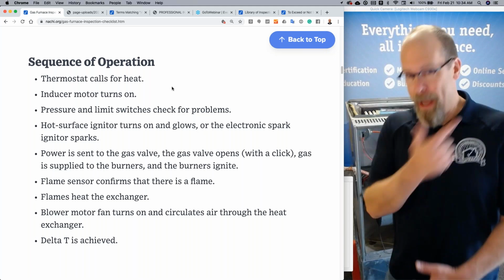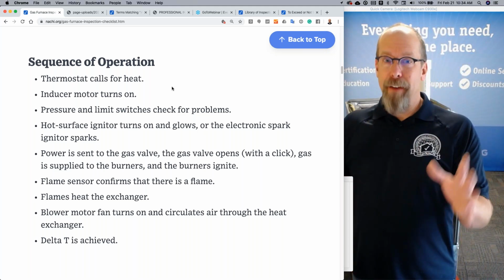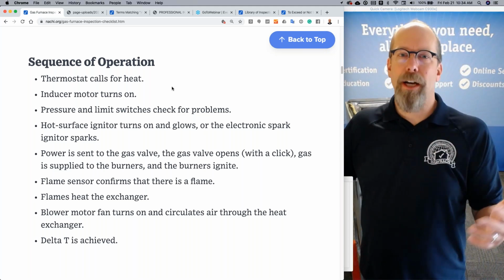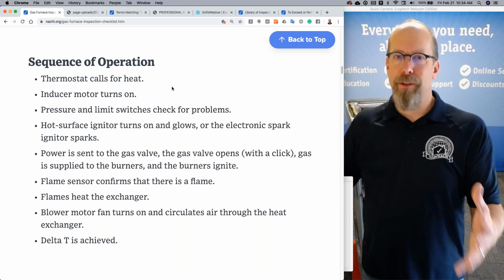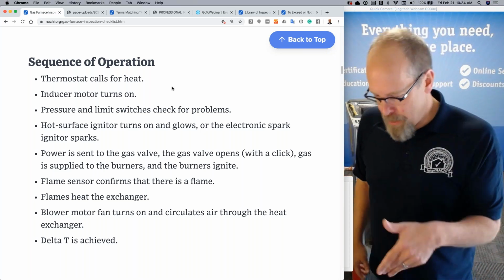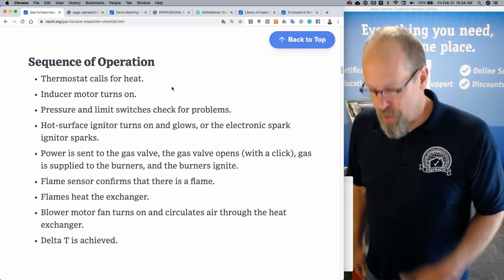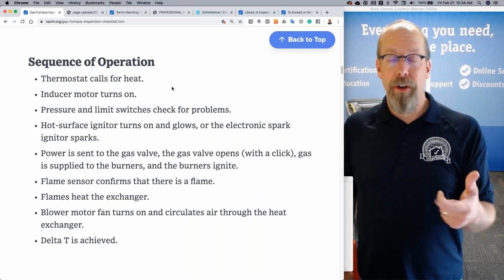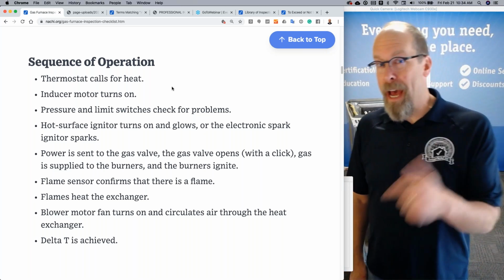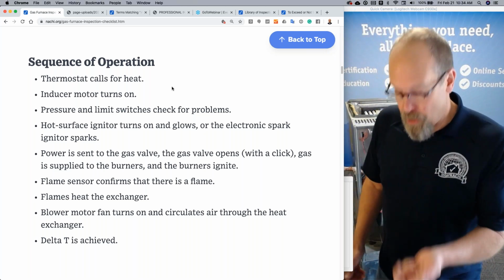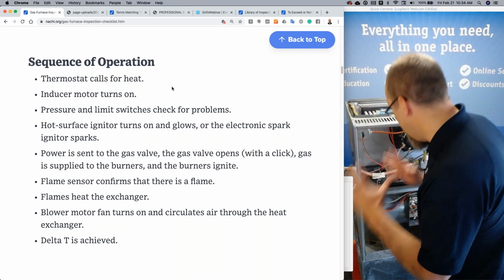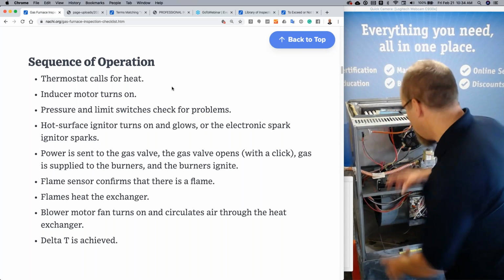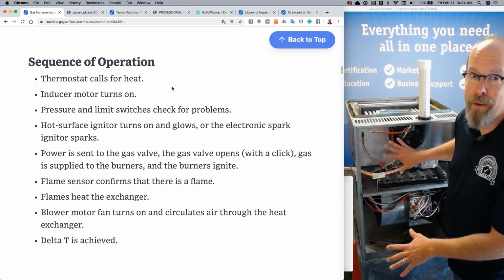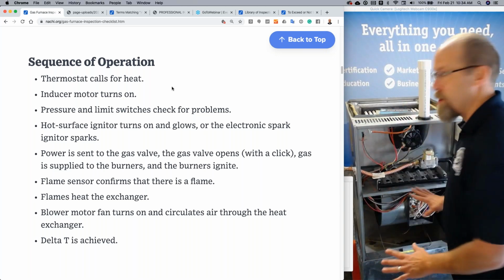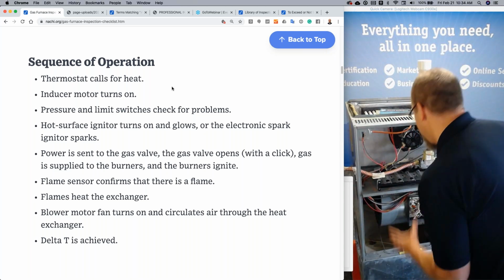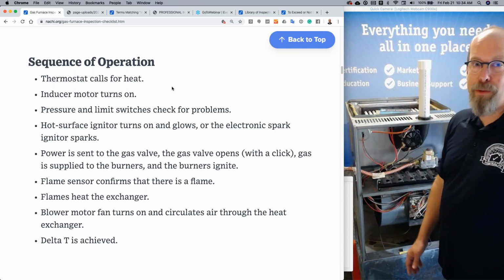And then I go back up. Well, I make sure it's safe, and if it's in the winter time, you could touch the ductwork and feel that there's an operating system. Turn the system off with the shut off switch. Go upstairs, turn the thermostat on, call for heat. Go back downstairs to the system, turn the service switch on, and get ready. And I hunker down, I take the panels off, the front burner panel, leave the blower door on, and I get ready to watch the sequence that we just went over.